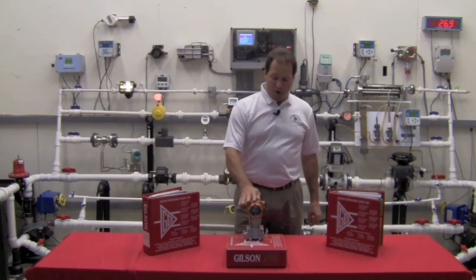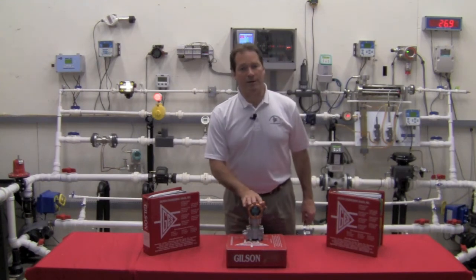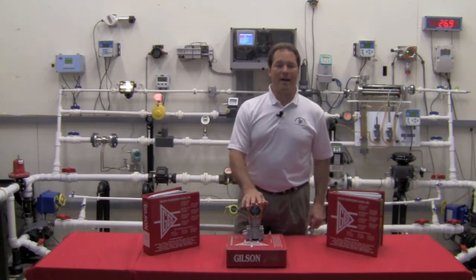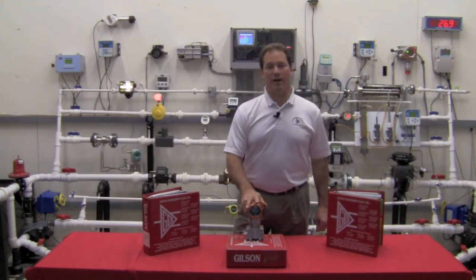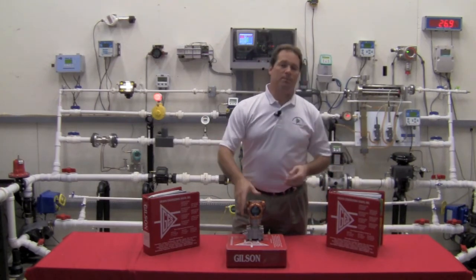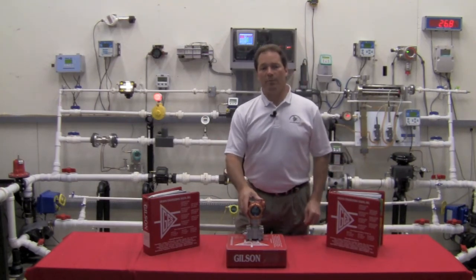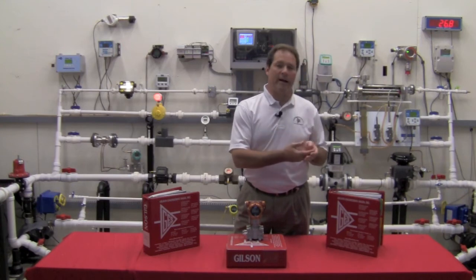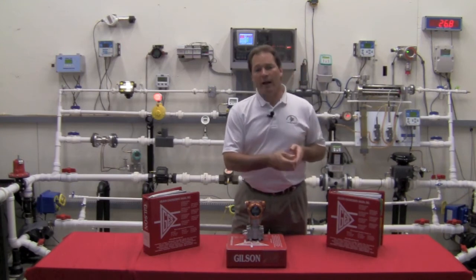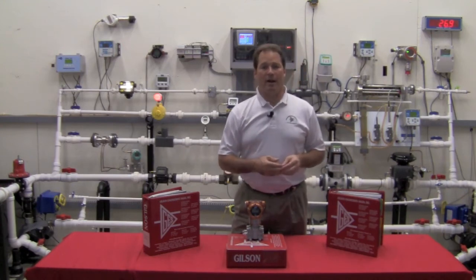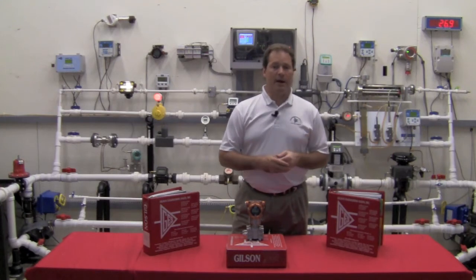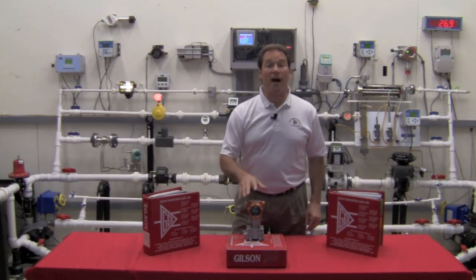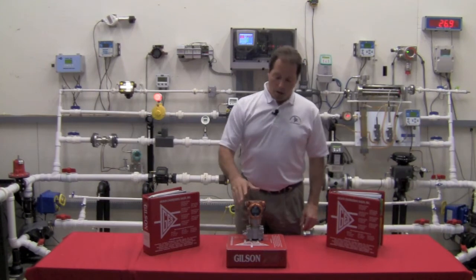The calibration on this unit is unlike anyone else in the industry. Most people will provide a 3 to 5 point calibration. That means if you're set up for 0 to 100 psi, they're going to calibrate it at 0, they're going to calibrate it at 50, they're going to calibrate it at 100. The higher quality manufacturers will make it 5 points instead of 3.